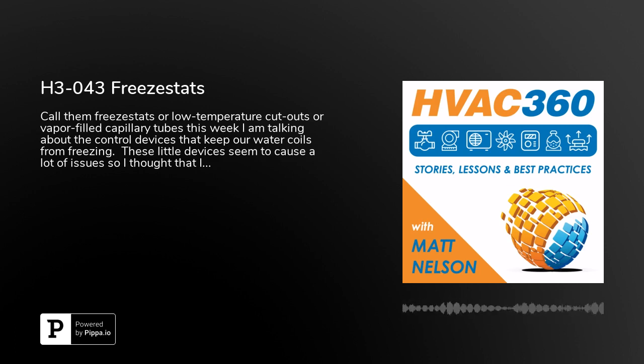Typically, and I've seen this in cases where the averaging sensor for the unit actually got switched, so it was on the downstream side and the freezestat was on the upstream side. That's a no-no. Typically, they're not going to put two sensing elements on the same side of the coil. So you want to have the freezestat on the downstream side of your coil. All right, now we have that explained.